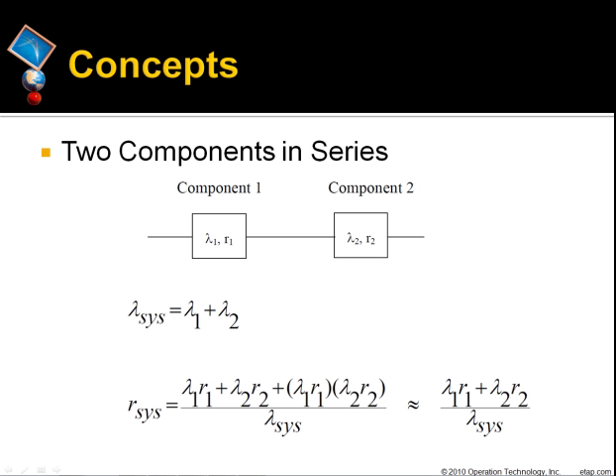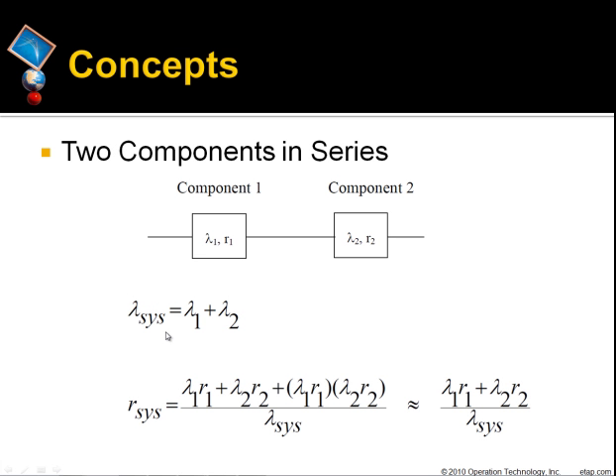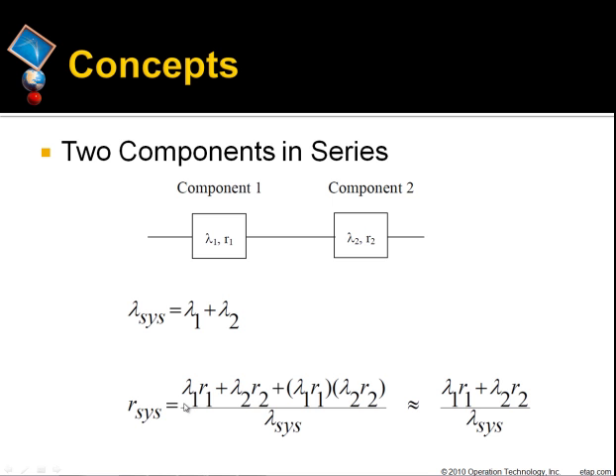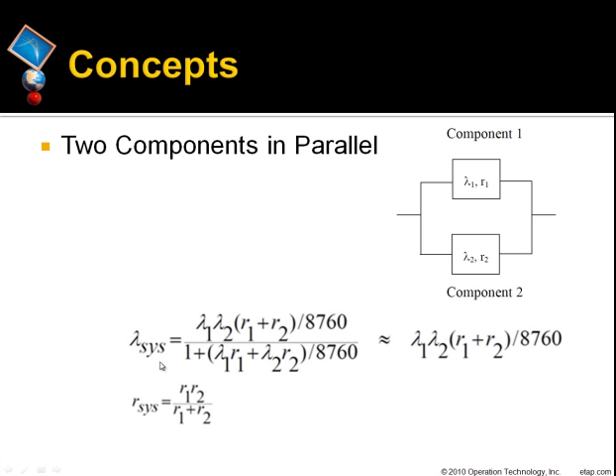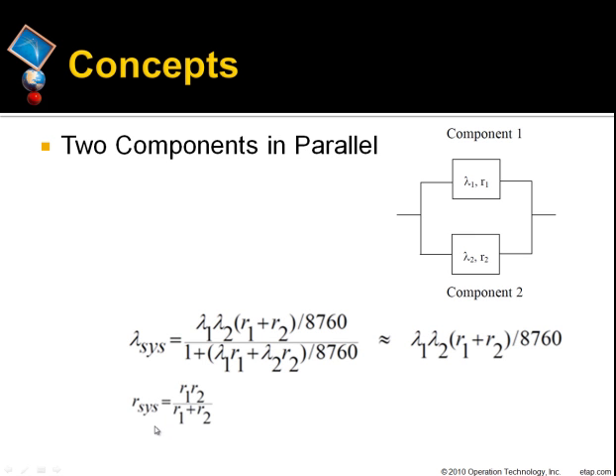For two components in series, the total failure rate, represented by lambda of the system, is the sum of each component failure rate, and the total failure duration, R of the system, is calculated with the equation shown. For two components in parallel, the total failure rate, lambda of the system, and total failure duration, R of the system, are calculated by the equations shown.